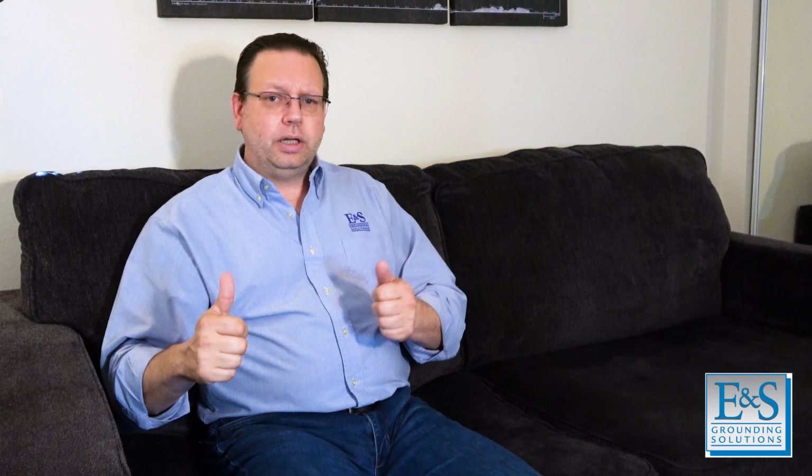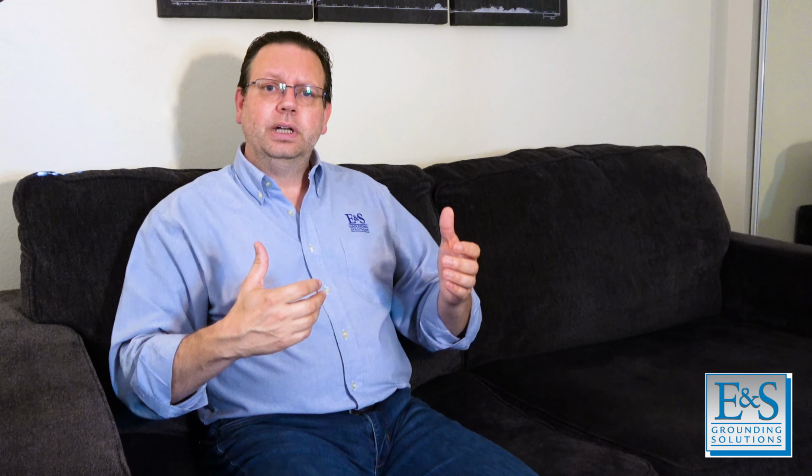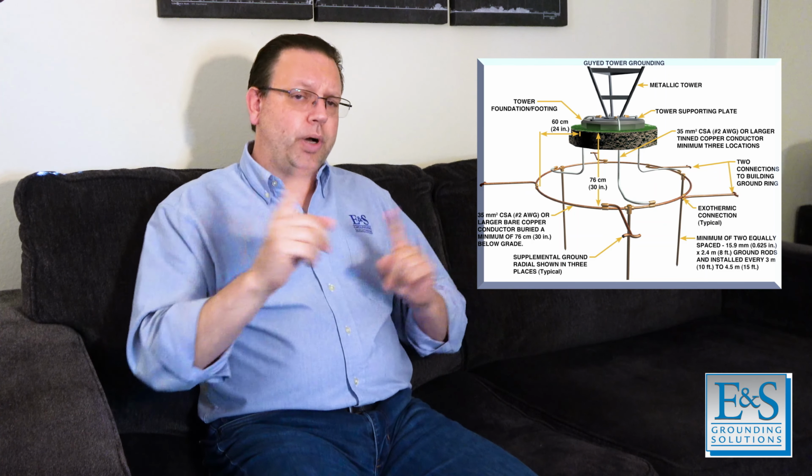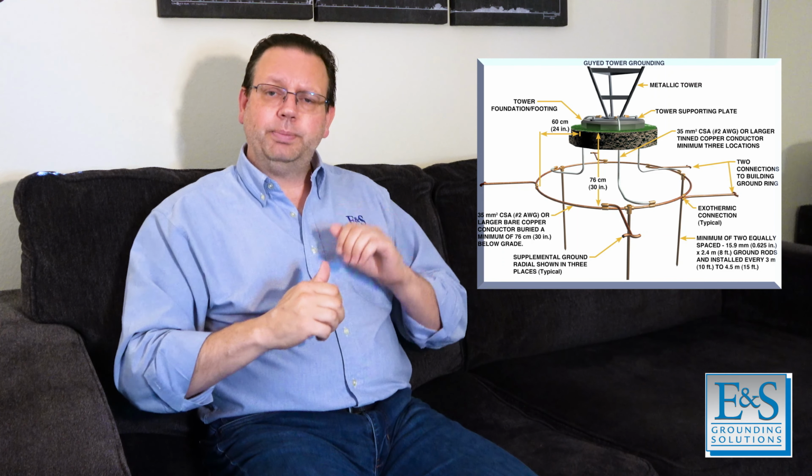It's an unintentional connection allowing neutral currents to travel back. It is not because you added an extra connection or added another ground rod. These don't cause loops at all. In fact, when it comes to a ground loop and the idea of a ring around a building, we actually like those. A ground ring is one of the most effective electrode systems we know of, circumnavigating your building and bonding it up to the building steel and up into your system.